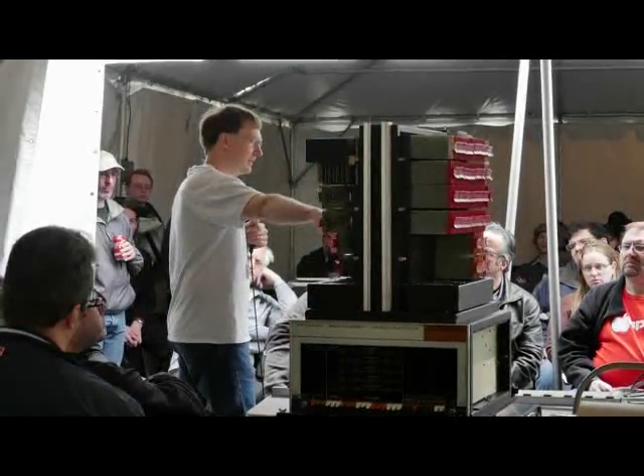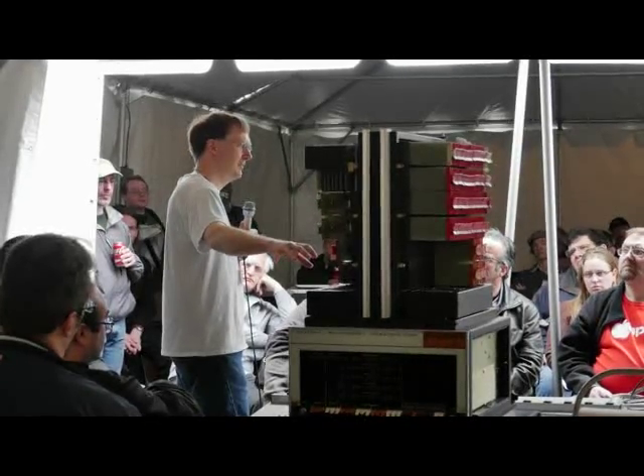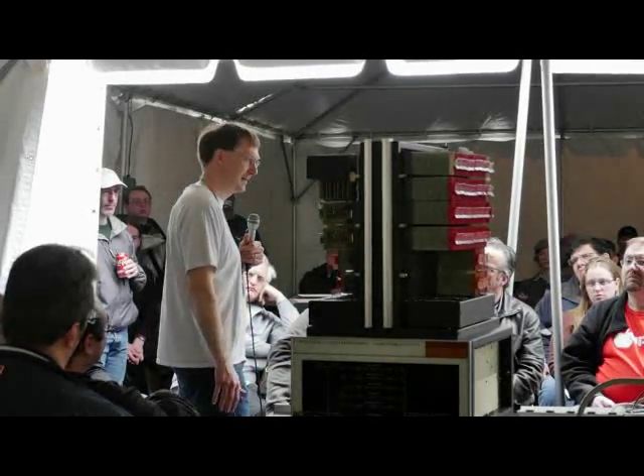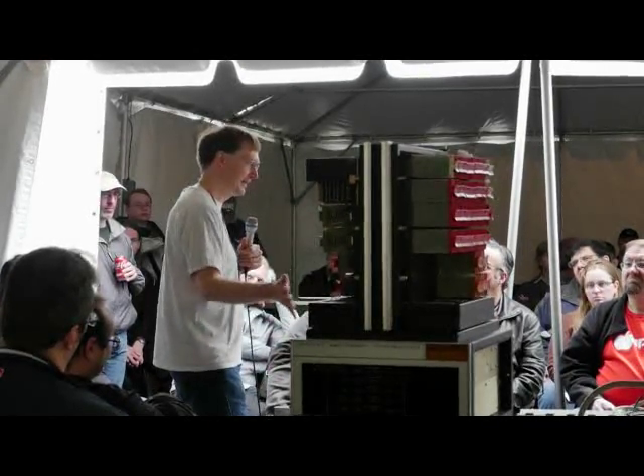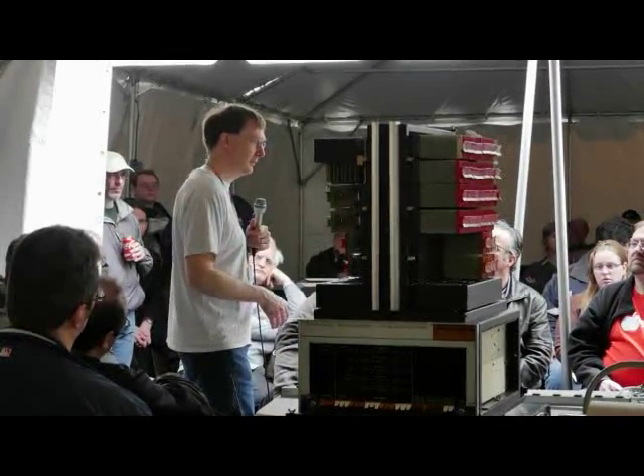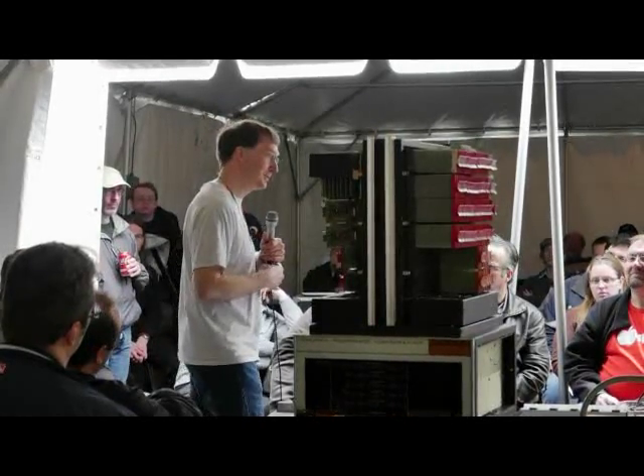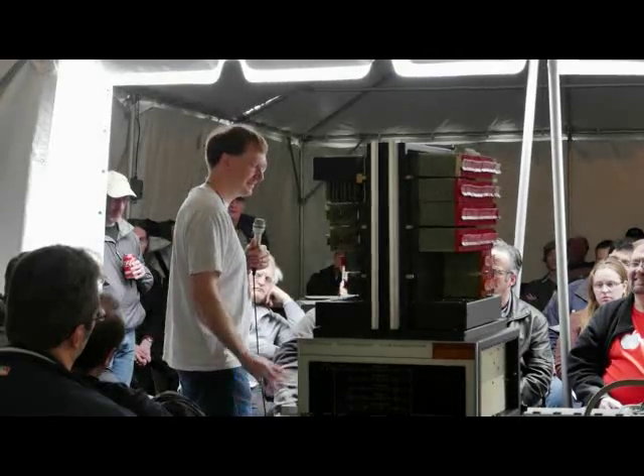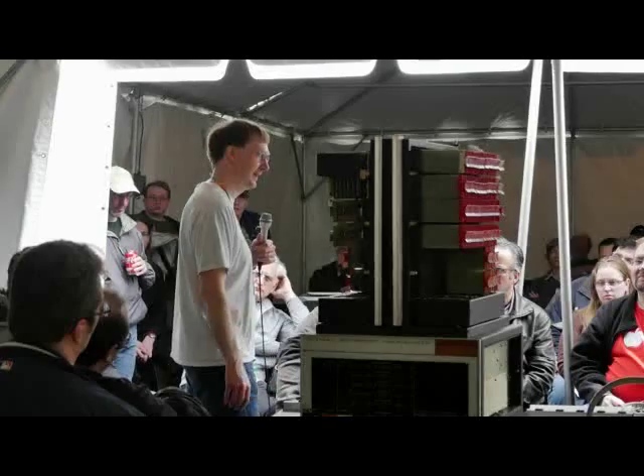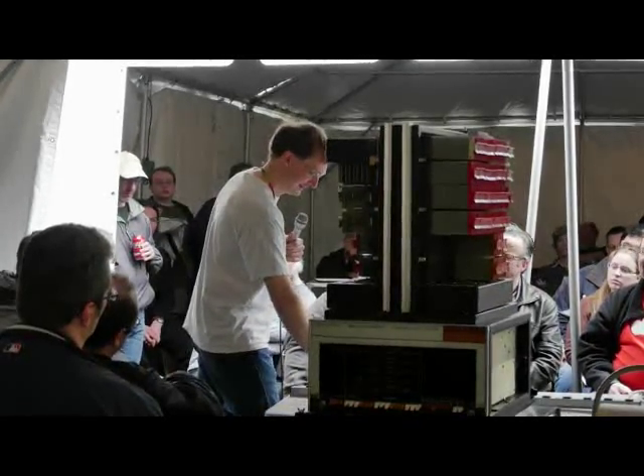And it also has in the power supply for the ferroresonant transformer. Most of the power isn't really fully regulated electronically. There's a weird technology with transformers. You can regulate voltage, which is called ferroresonant, and that's what this uses. Those have an AC oil-filled capacitor, which in this time frame is PCBs, which was super fun clean-up time. So that was removed because they tend to go bad, explode, and spew boiling, contaminated oil around, which is not a good thing.